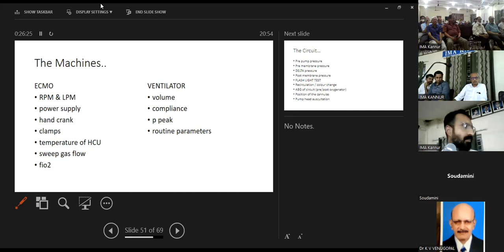And the power supply you have to check daily. The hand crank, which is very important. Sometimes during loss of power supply, you may have to use the hand crank to run the pump. So you should have the hand crank nearby. The clamps, temperature of the heater cooler unit, the sweep gas flow, and the FiO2. In the ventilator, we check the volume, the compliance, the peak pressure.